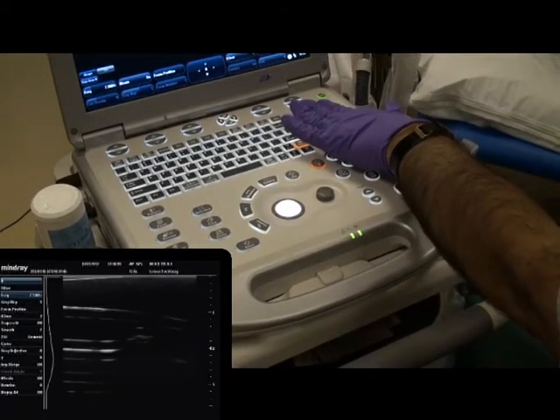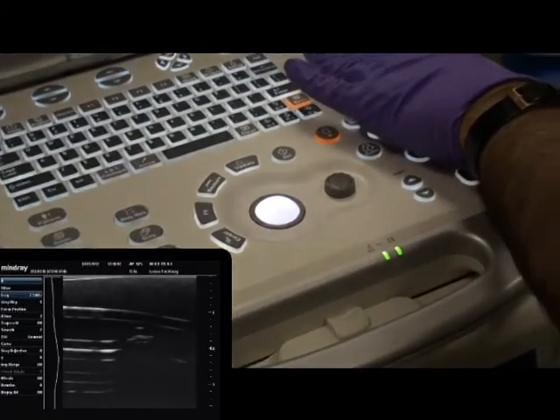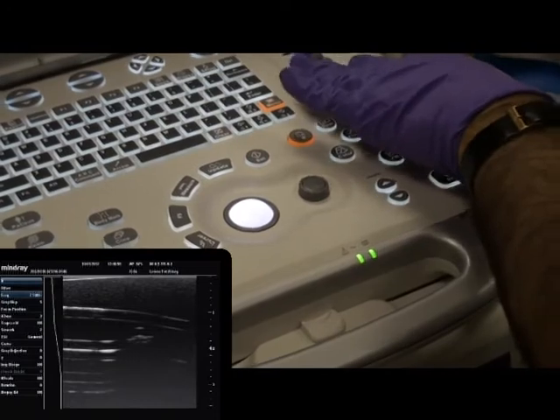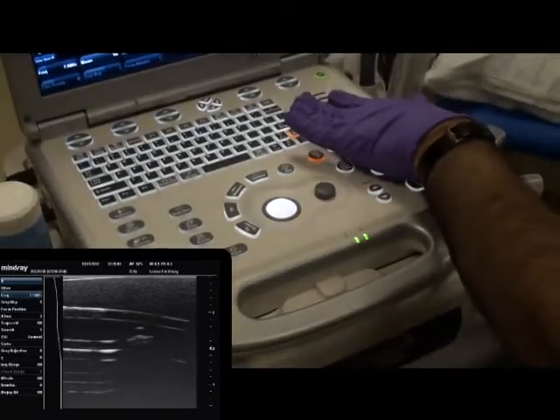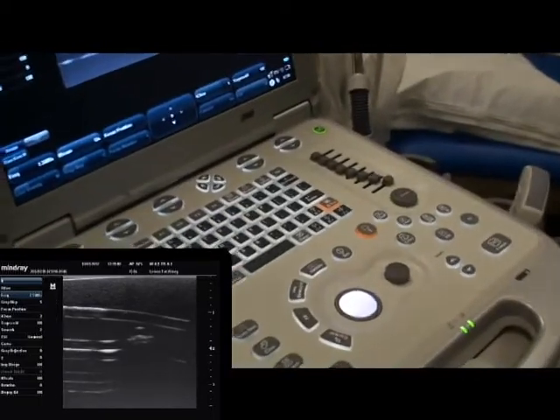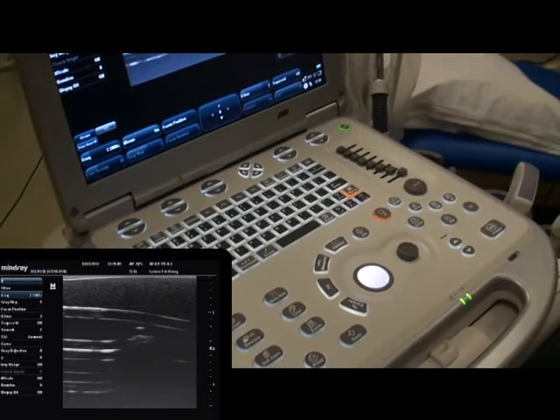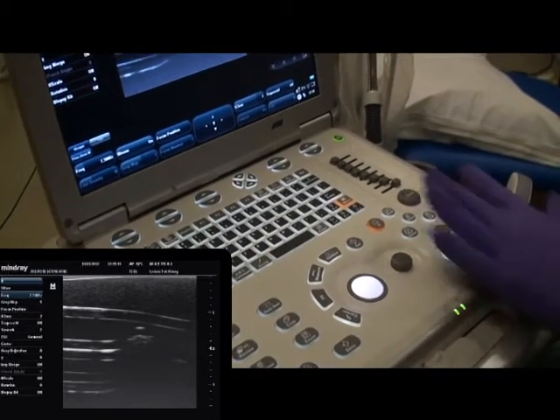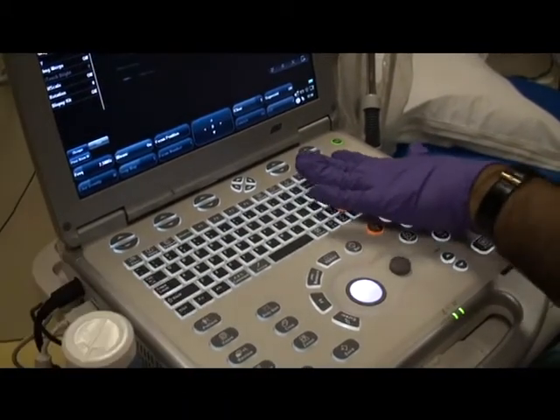The time gain compensation sliders on the top right of the keypad change the amplitude of the signal at various depths of the ultrasound field. This is to compensate for sound attenuating the deeper it goes into the patient. Use this oblique arrangement to amplify the deepest and therefore most attenuated part of the field.